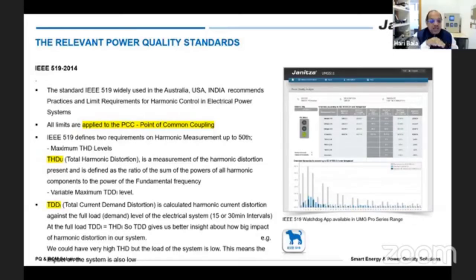And they call it the calculated harmonic distortion against the full load level of the electrical system. Say, for example, a consumer has a 1000 kVA load, and it's the current for the 1000 kVA which is used in the last 12 months. They have said, even if you may have a higher contract demand, you can still have a lesser demand actually happening in your network. So you can take the last 12 months and calculate the total demand distortion. So this is another point which is coming up in the power quality standard IEEE 519.